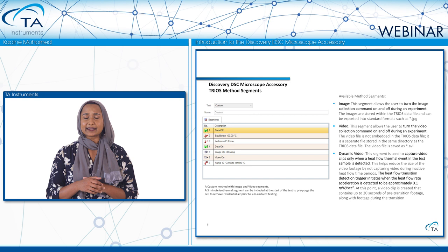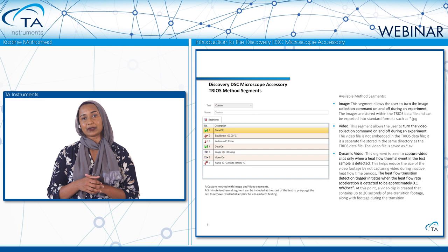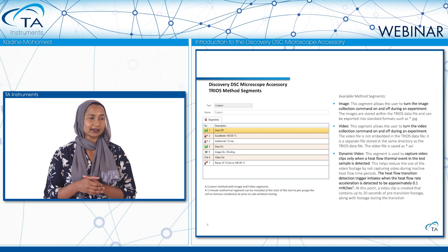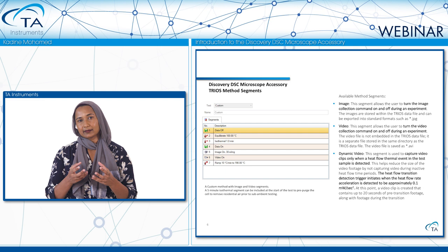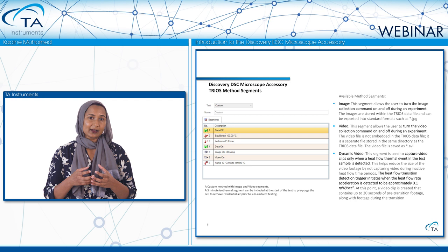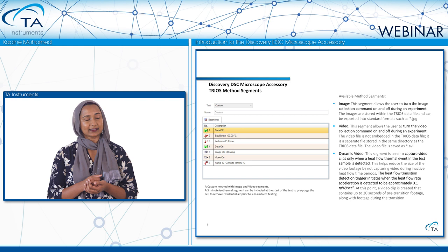If you're doing experiments that begin at subambient temperatures — say equilibrating at minus 100 degrees — I suggest including a five-minute isothermal at the beginning of the experiment. This pre-purges the cell to remove any residual air that might be present, which may have humidity and can condense onto the sapphire windows. You want to prevent fogging of the sapphire windows, so placing a five-minute isothermal hold at the start before equilibrating to subambient temperature would be ideal.